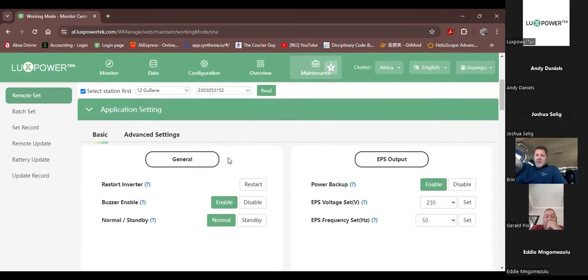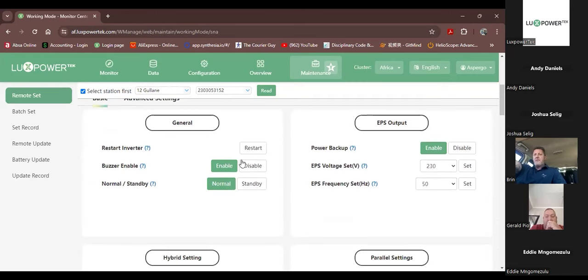All right, so here you can see now that we have basic and advanced settings. In the basic settings, under general, we can restart the inverter. Buzzer enabled simply means exactly what you're used to: whenever you press the keypad on the machine, it makes a noise. So you can enable or disable that buzzer. The normal and standby button puts the machine into standby mode. For instance, if you need to change your battery type or do any other settings where you get an operation failed error code 3, you must remember that you cannot change the battery settings while the machine is charging or discharging the battery.